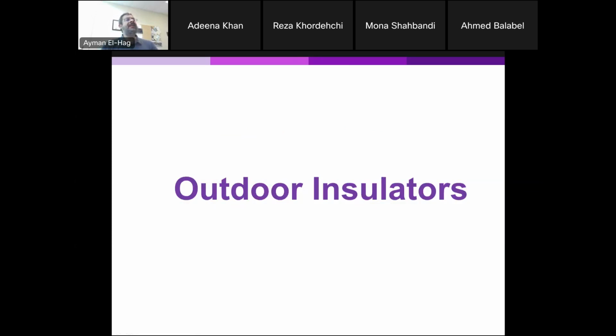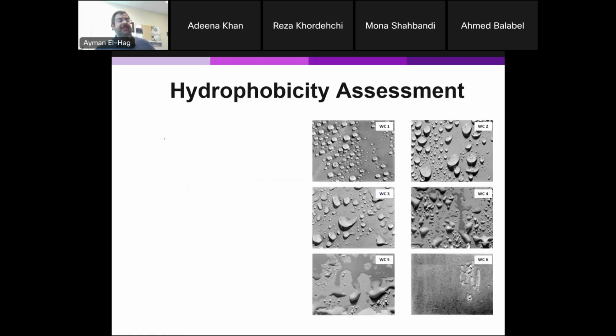Now, what are the field tests that we do for the outdoor insulators? One of the tests we do on the site is the hydrophobicity assessment. We said that we have polymer insulators and ceramic insulators, and we'll talk about the difference between the two in detail in the coming week. But one of the properties of polymer insulators is that their surface is hydrophobic when they are new. Hydrophobic in the sense that when you have wetting on the surface, the water will be small, discrete droplets, not connected to each other. And this will prevent any development of a current on the insulator surface.